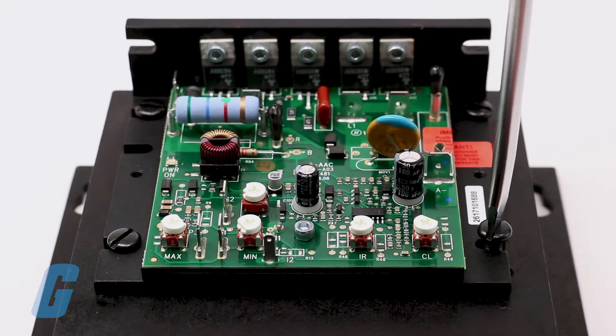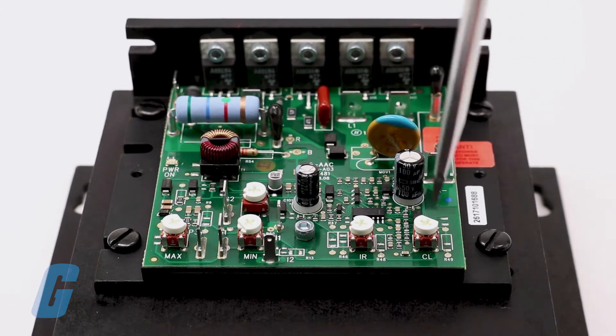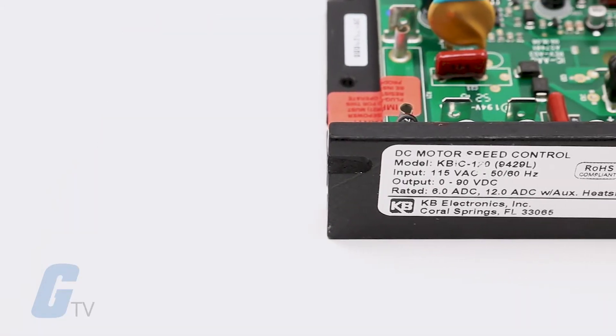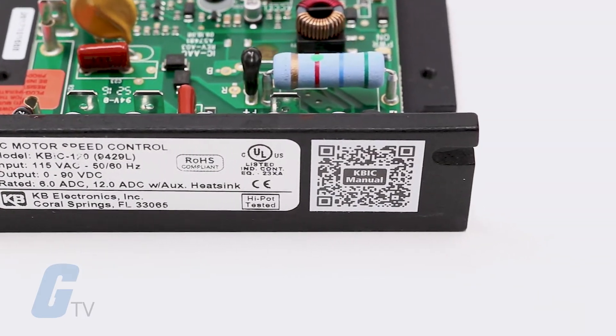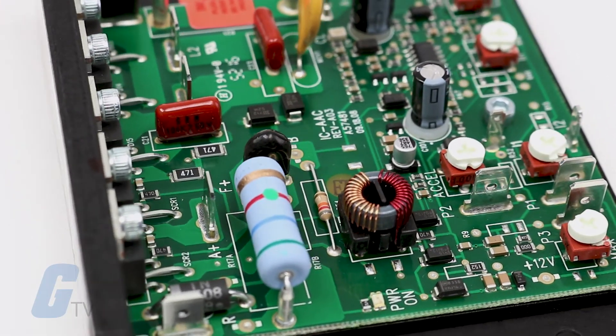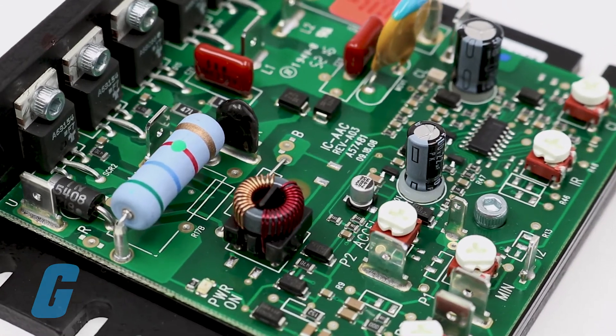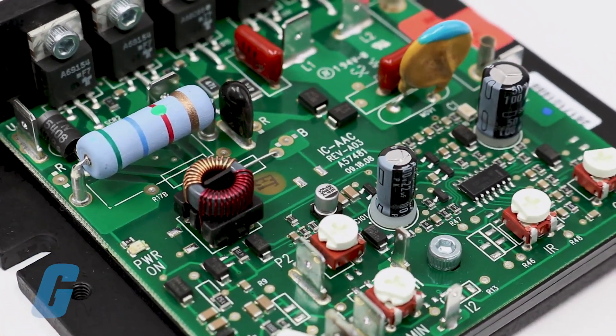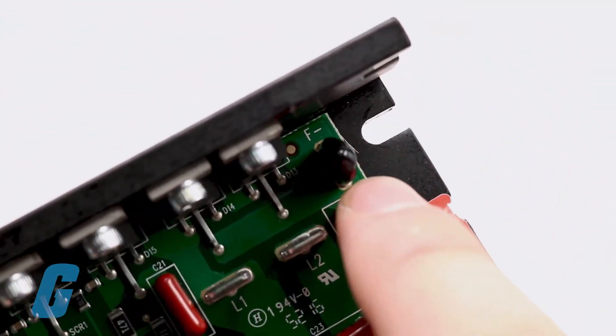Additional versatility is achieved by using the auxiliary heatsink, which is used to double the horsepower rating of each model. There are six types of KBIC drives that either have an AC line voltage of 115 or 230 volts. The KBIC can also be operated in a voltage following mode by supplying an isolated analog signal of 0 to 9 volts DC with the input terminals P2 positive and F negative.